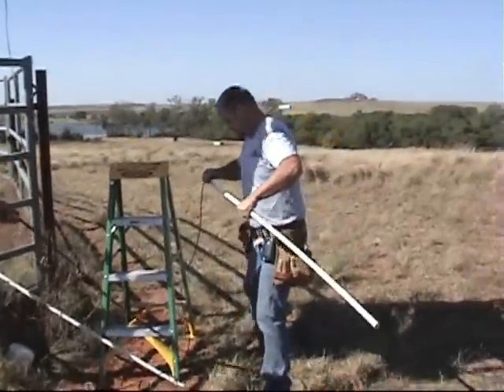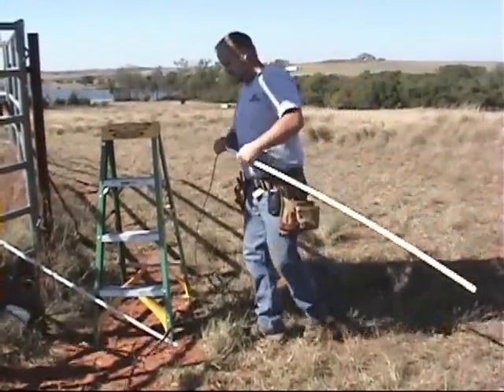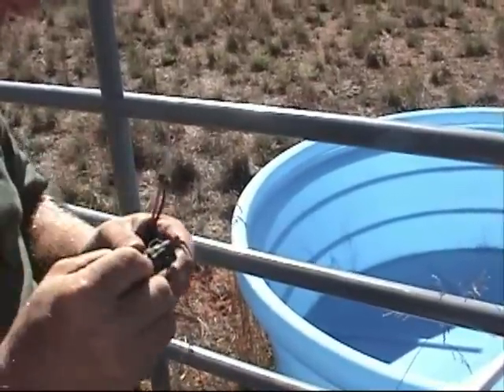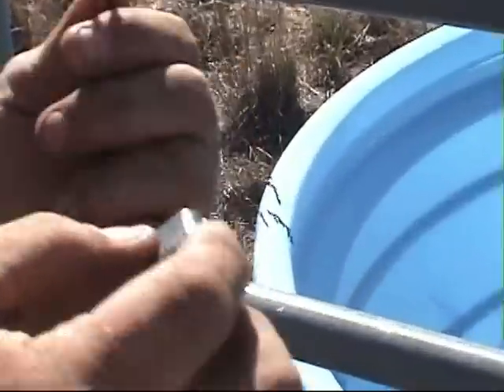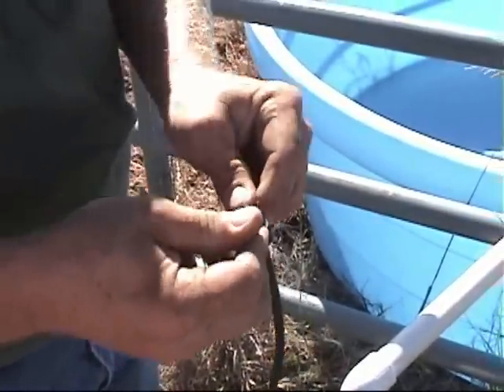I'm going to run our sensor wire in some half inch conduit here to attach the connection. On each one of these there's a little B for black to put your black wire, and then your A will go in the opposing terminal.